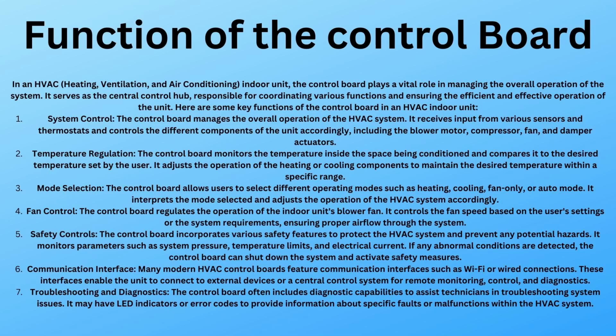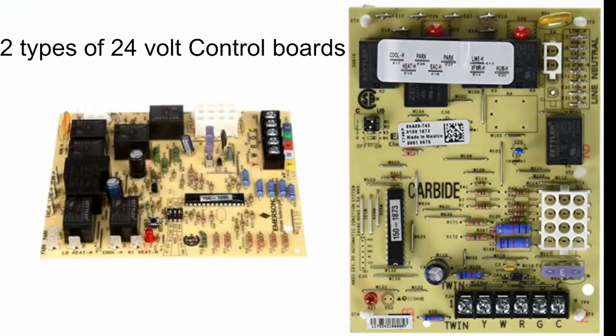The control board often includes diagnostic capabilities. Remember I told you about the flashing. It assists the technician in troubleshooting system issues, and may have LED indicators or error codes, and that's what I was trying to tell you. It has a little flash. Those are your error codes and LED indicators. So it's a little LED bulb that's red. It could be yellow. It could be blue, whatever they decide they want to use. On White Rodgers, it's red. And it provides information about specific faults or malfunctions within the HVAC system. So let's go ahead and take a look at that control board.